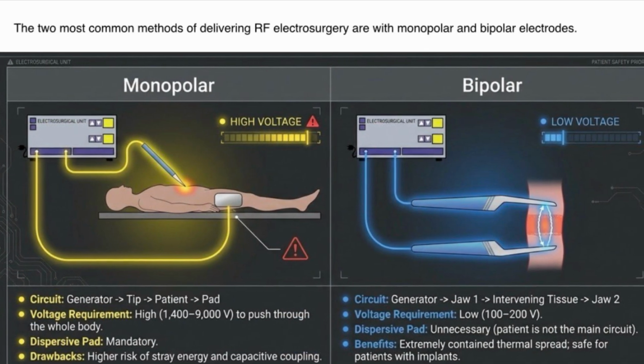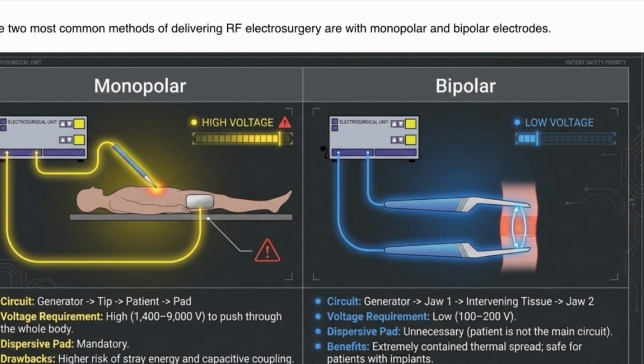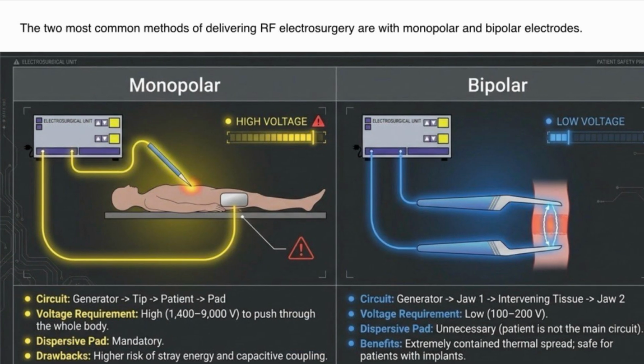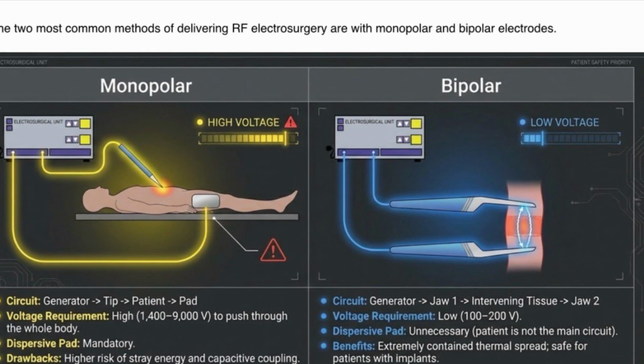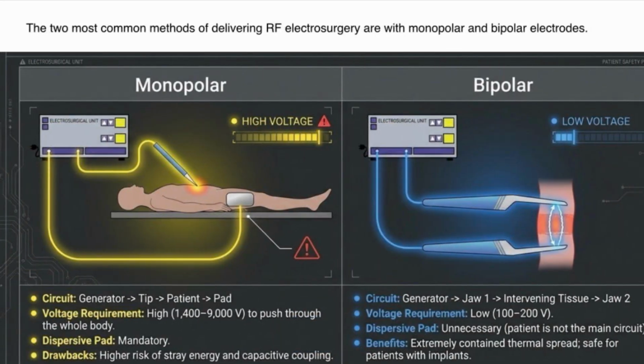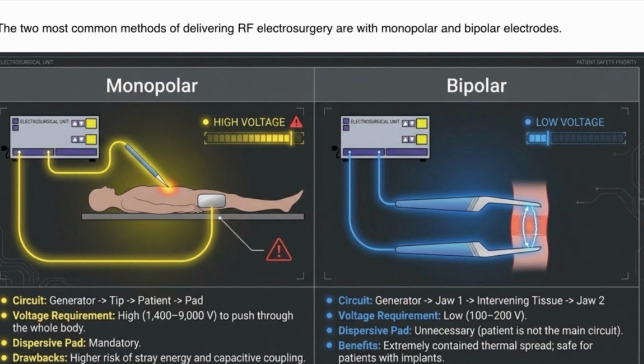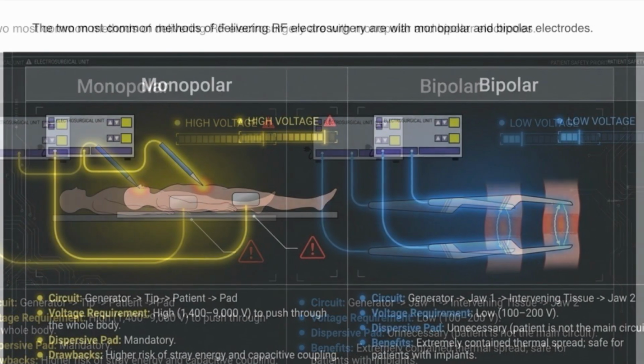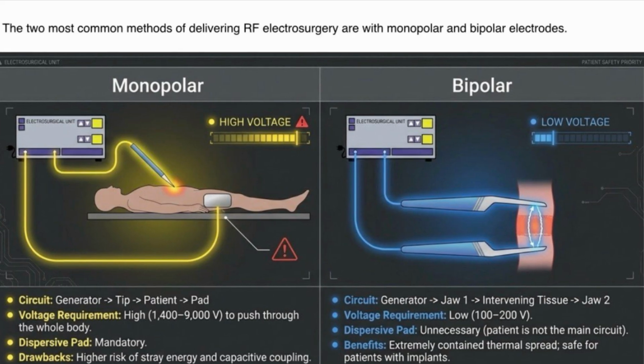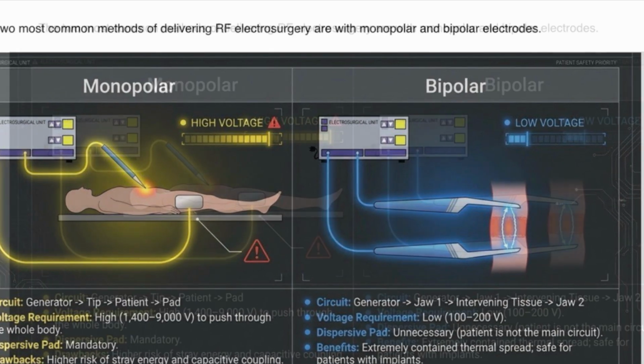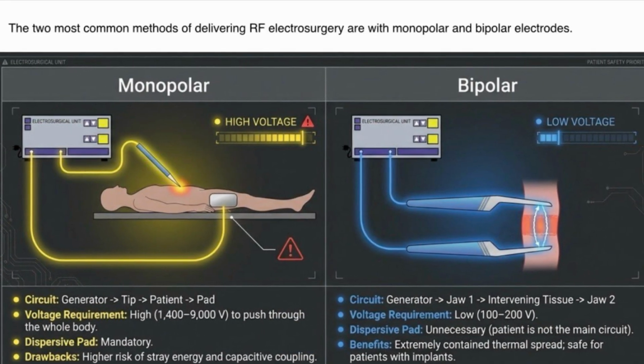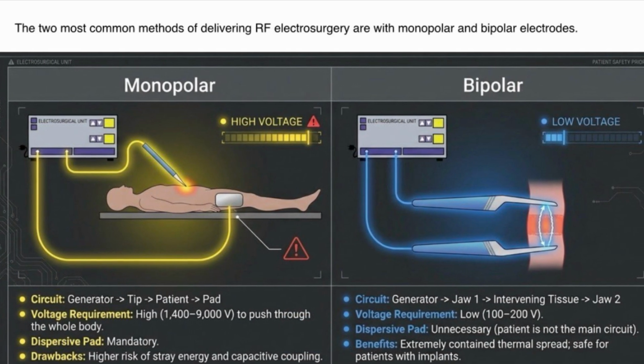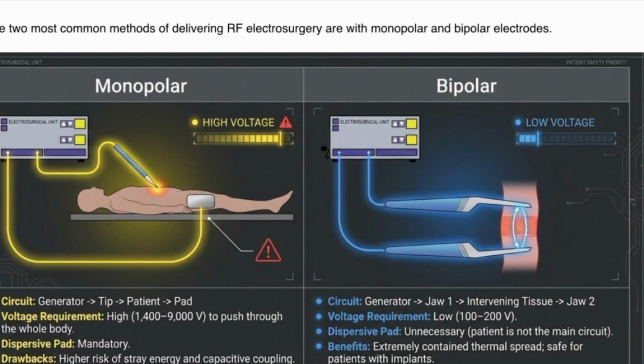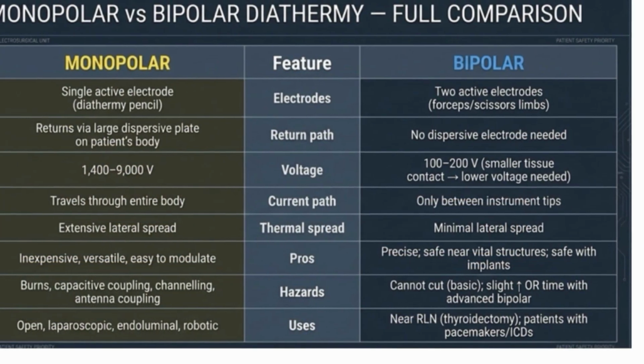The two common methods of delivering radiofrequency electrosurgery are with monopolar and bipolar electrodes. In monopolar, the circuit is generator, tip, patient, and the pad. The voltage requirement is high, 1400 to 9000 volts, to push through the whole body. The dispersive pad is mandatory. Drawbacks are higher risk of stray energy and capacitive coupling. In bipolar, the circuit is the generator, jaw 1, intervening tissue, and jaw 2. Voltage requirement is low, 100 to 200 volts. A dispersive pad is unnecessary. Benefits are extremely contained thermal spread, and it is safe for patients with implants.